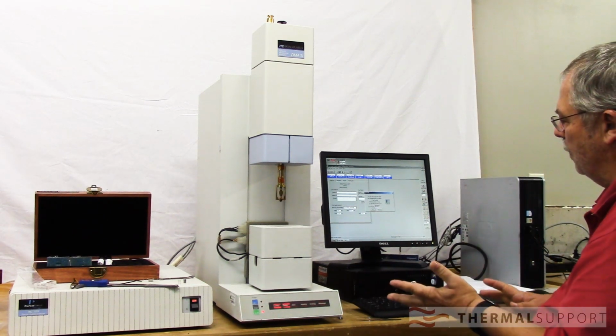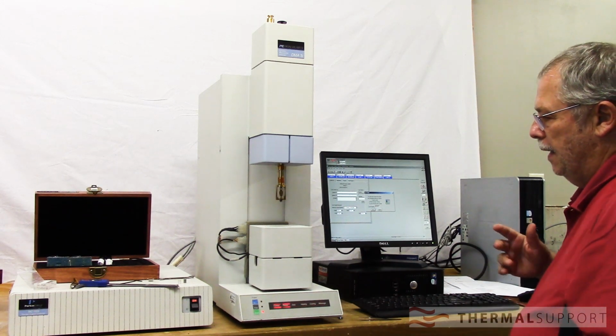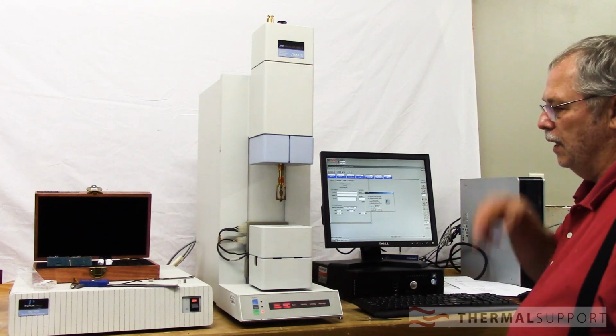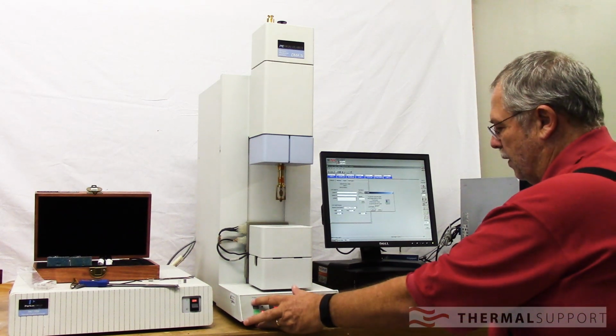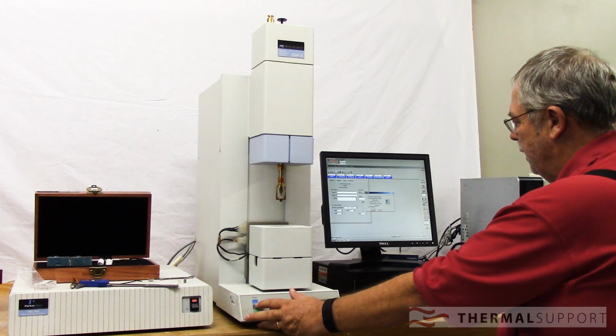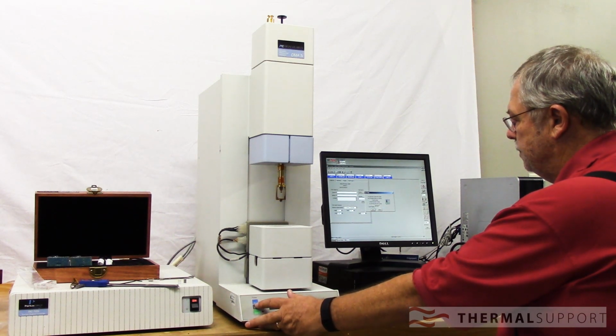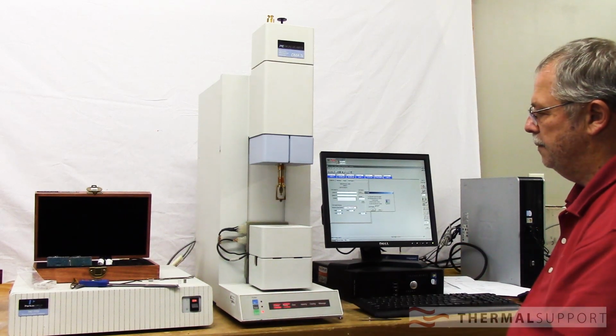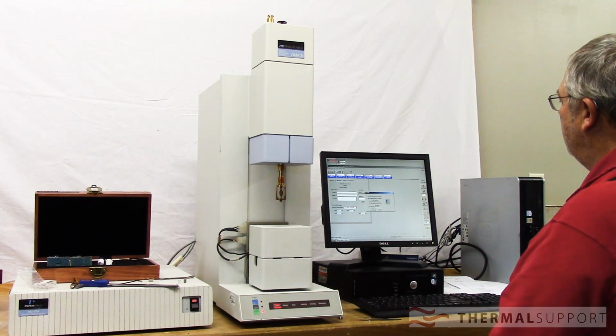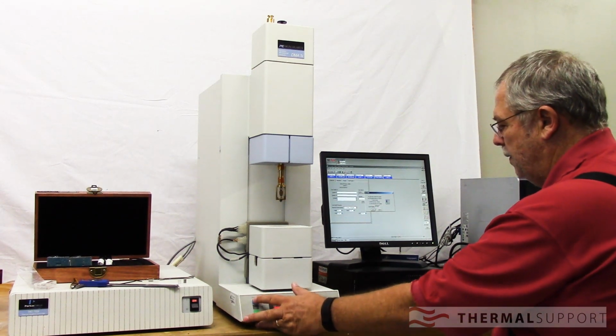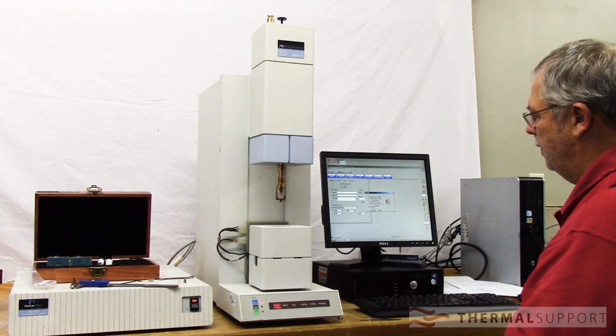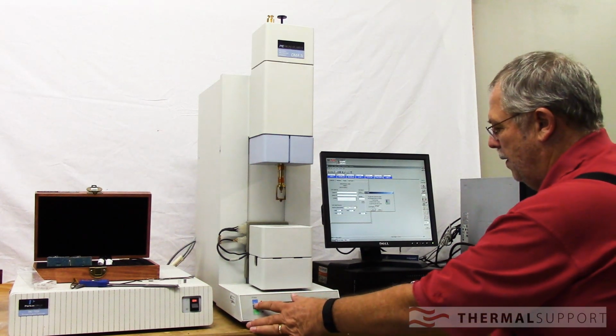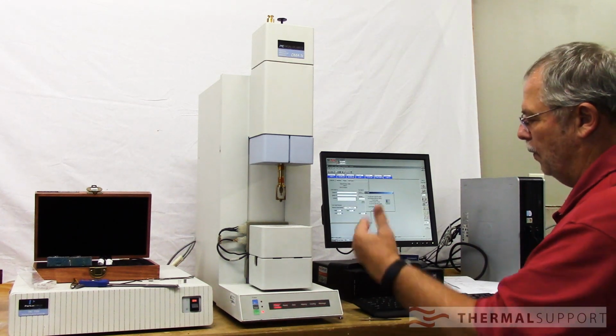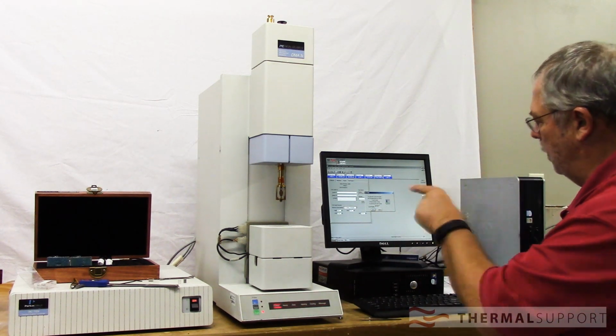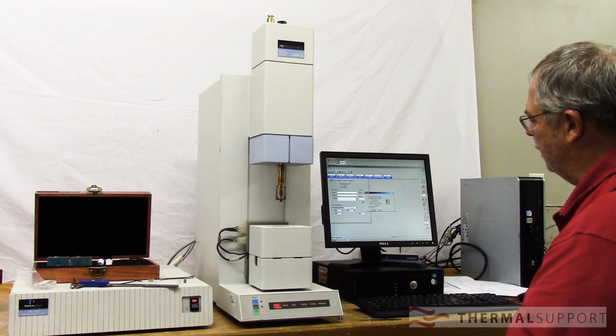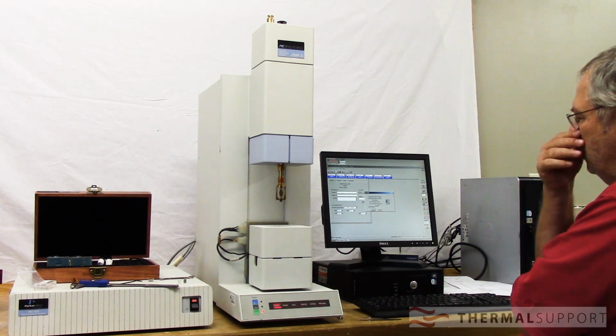So that comes back at 13,277. I always like to throw out the first one because you don't know if we set the platform on, if you bound anything up or anything. So we're going to go ahead and do that twice more. We'll hold, we're going to come back down. 13,228. Hold, back down. By the way, I put a hold in between so we keep everything consistent. We're not sitting there bumping it. 13,277.